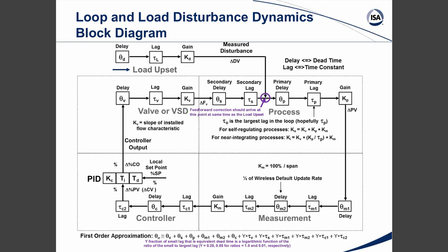One thing we have learned, interestingly enough, is that the feed forward summer, at least in the DCS system we were using, if there was a negative value being computed of the feed-forward signal due to the steam generation being greater than steam usage in that header, even though you had the feed-forward scale set to be zero at its low value, and say the valve had a capacity of 0 to 100,000 pounds per hour, and you had your feed-forward scale set at 0 to 100,000, we found that internally in the feed forward summer, that negative value was taken into account, and it would cause a disruption in the feed forward signal when that changed.